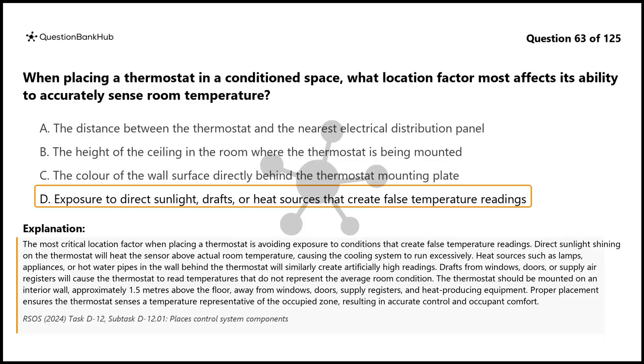The thermostat should be mounted on an interior wall, approximately 1.5 meters above the floor, away from windows, doors, supply registers, and heat-producing equipment. Proper placement ensures the thermostat senses a temperature representative of the occupied zone, resulting in accurate control and occupant comfort.